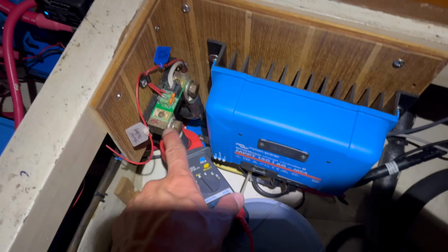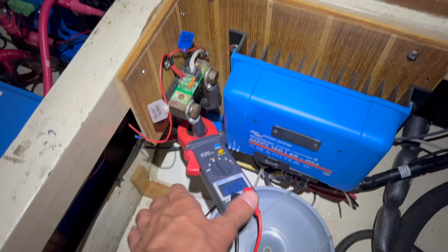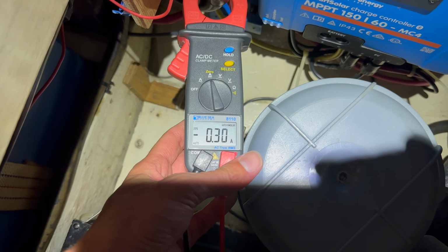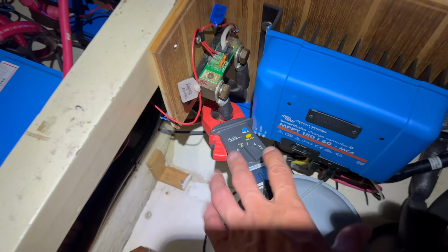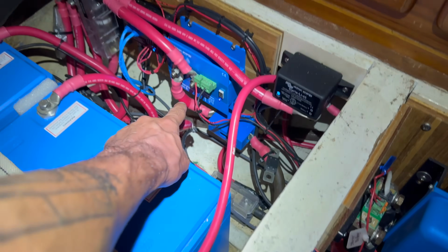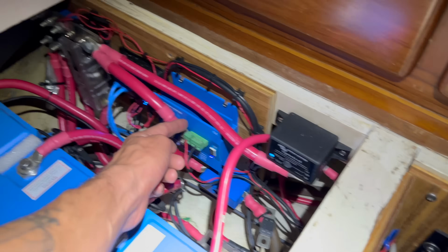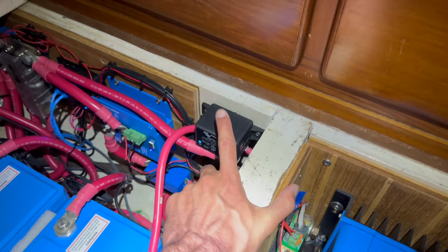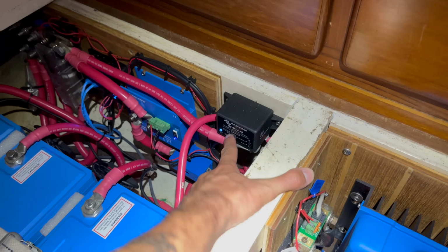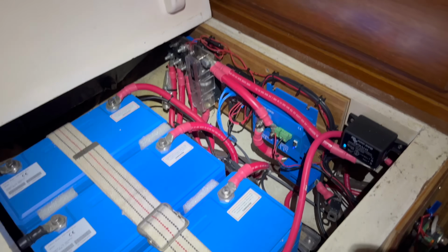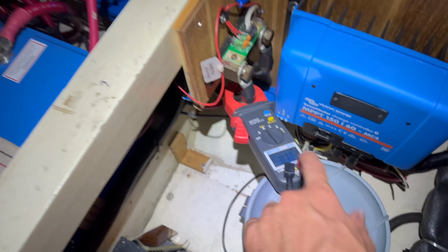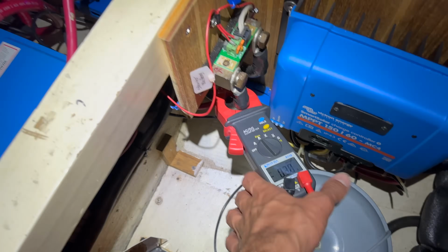So here's the shunt, which is what the battery monitor is reading off of. You can see we're only pulling 0.3 amps right now. I'm assuming that's just because of the battery management system, the BMS, and the battery protect, which is another device that connects the two battery systems, the starter and the house battery, to charge them both. I'm assuming this 0.3 of an amp is just the running cost of having these things up and running. I think it's safe to say we can do a zero current calibration on the batteries, since 0.3 amps isn't giving us an accurate calculation.